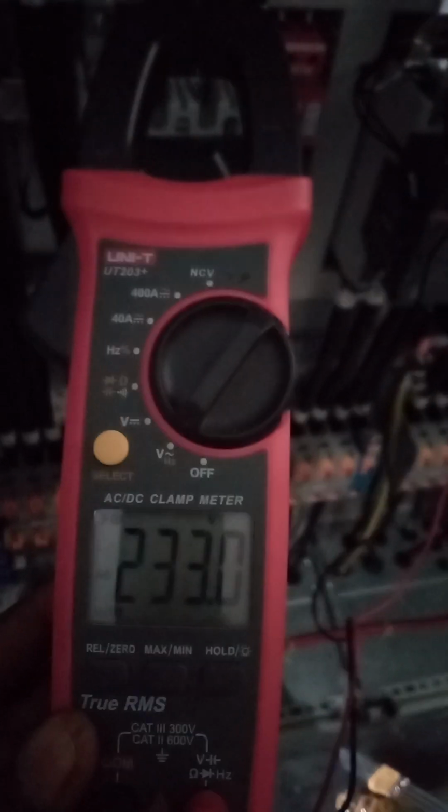However, from this bus, from these breakers, we're supposed to be having generator feeding this contactor, and this contactor is the one that supplies the load through the generation container and to the grid. So let's check the input from the generator whether it comes into the contactor. Line 1 and neutral, 233.0. Line 2 and neutral, 228.8. Line 3 and neutral, 229.4. Okay, we confirm that this is fed well. It's having power. But from here, it's supposed to pass through this.